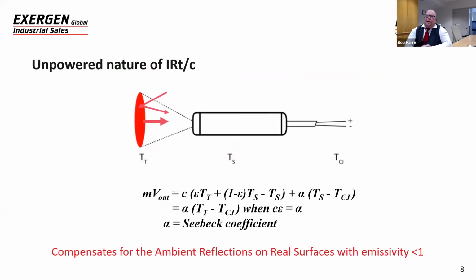The other thing that we do here at Exergen when we calibrate the IRTC is we calibrate to real world conditions. As I explained earlier, there are effects of the emissivity and the reflections that will affect what the target is emitting. And typically in the real world, you're not measuring black bodies. We're measuring things that aren't perfect emitters. So you could be measuring wood, paper, glass, ink, blood, anything that's high emissivity that is obviously not a perfect black body. So there are a variety of different emissivity numbers for the different materials.